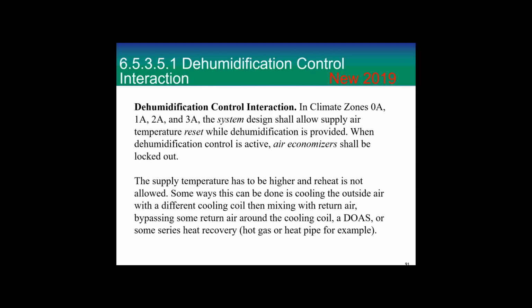But the fall and the spring shoulder months are the most terrible for humidity, because your unit doesn't run and it's really high humidity outside in these climate zones, 2A, for example. And so it's terrible, because if you don't have some way to go into a dehumidification cycle, you will cause humidity problems in the building. Humidity problems cause mold problems. Mold problems cause the building to fall down. So it's a horrible thing to do. But anyway, there are a lot of people from the cold part of the country in California on the committee. So even if some of us voted against it, this is part of the standard. So the supply temperature has to be higher and reheat is not allowed.